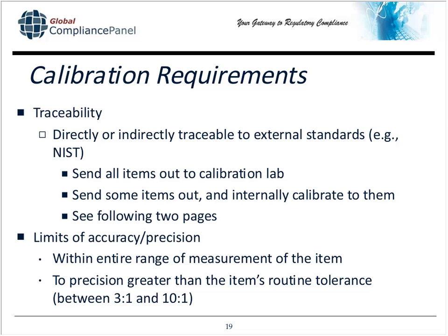You can't just use calipers, for example, and say, yeah, plus or minus a half inch, because if that caliper is used to measure quarter-inch tolerances, that's not enough. So you've got to look at the entire range of measurement of the item and then set your limits accurately. A precision greater than the routine tolerance is usually the way to go. I've seen it between 3 to 1, 10 to 1, whichever you prefer, as long as you make sure that the precision is greater than the routine tolerance.